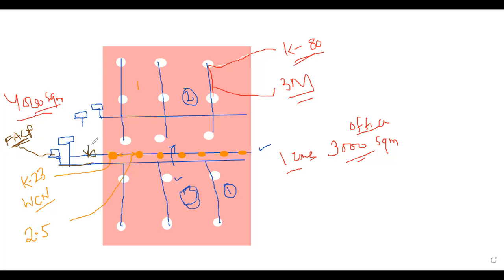Here we have a motorized butterfly valve in this water curtain system, and the second flow switch will be connected to that. Once it gives actuation, it will operate and open. Actually, we have done this innovation in one of our projects; some people may not know this.